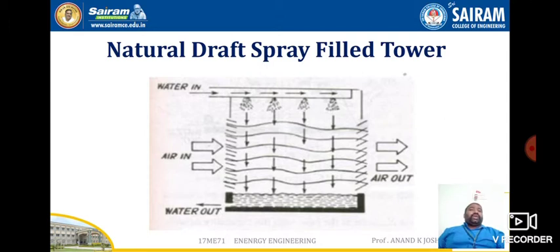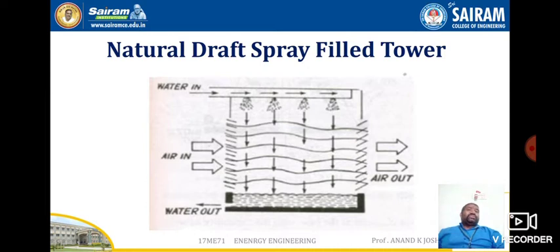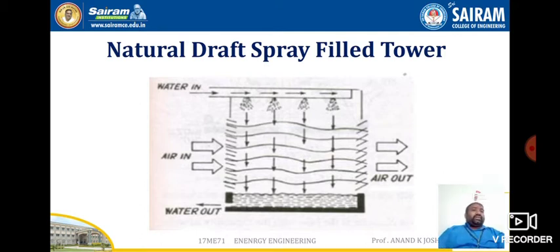In the natural draft spray tower, air enters through the lower side and flows across the unit in a transverse direction. The air circulation depends on wind velocity. The capacity of this tower varies from 50 to 100 liters per minute per square meter of base area depending on air velocity. These towers are used only for diesel plants where prevailing winds are not blocked by obstructions, and they are not used for high capacity thermal power plants as the cooling range is limited.